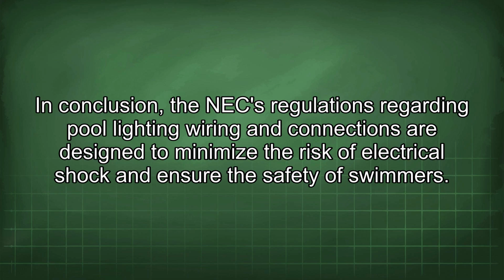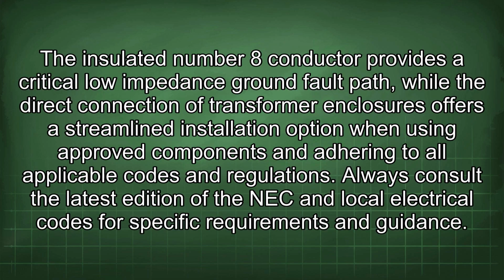In conclusion, the NEC regulations regarding pool lighting wiring and connections are designed to minimize the risk of electrical shock and ensure the safety of swimmers. The insulated number 8 conductor provides a critical low-impedance ground fault path, while the direct connection of transformer enclosures offers a streamlined installation option when using approved components and adhering to all applicable codes and regulations. Always consult the latest edition of the NEC and local electrical codes for specific requirements and guidance.